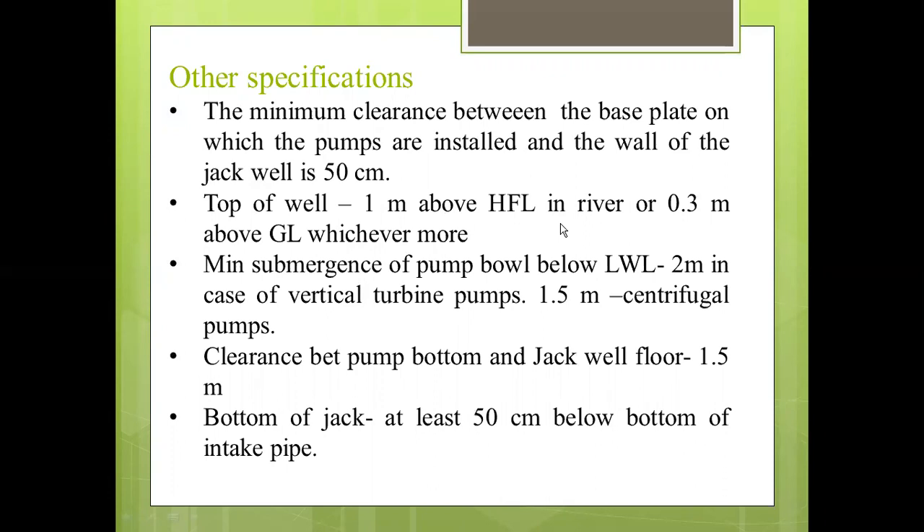The minimum submergence of the pump bowl below the lowest water level is 2 meters in the case of a vertical turbine pump, and 1.5 meters in the case of centrifugal pumps. The clearance between the pump bottom and the Jackwell floor is 1.5 meters. The bottom of the Jackwell should be at least 50 cm below the bottom of the intake pipe.